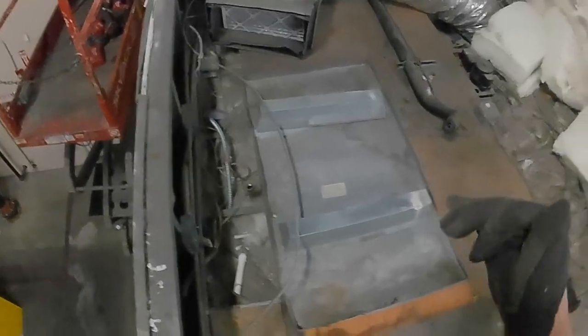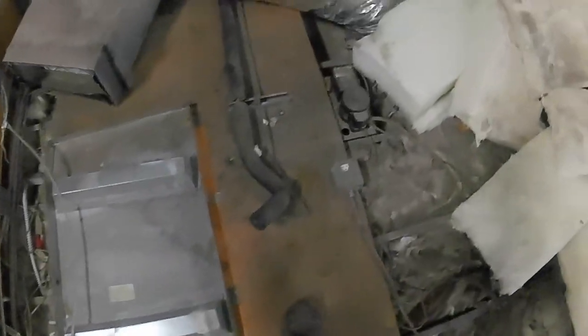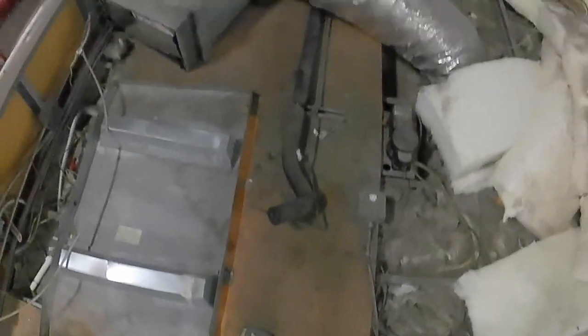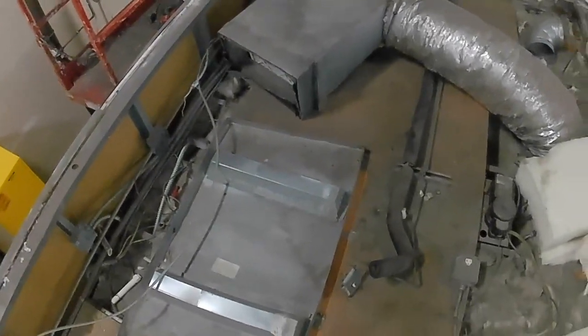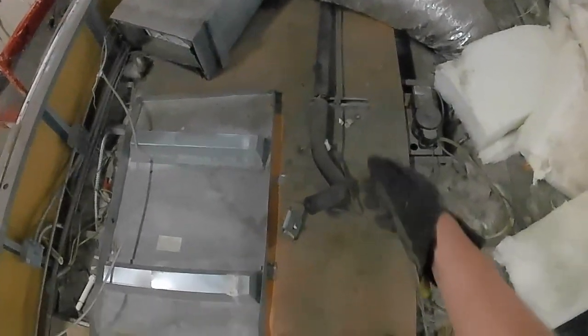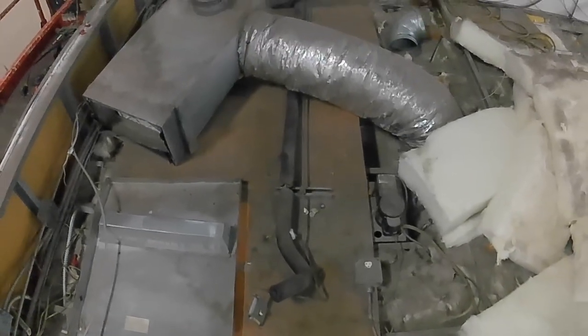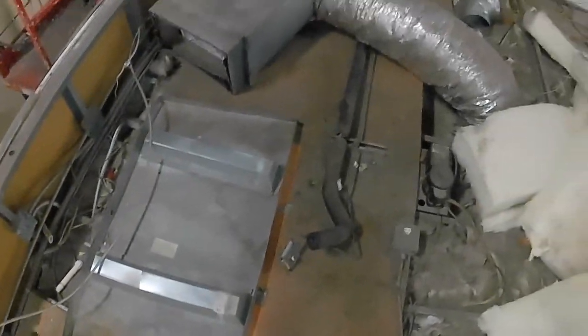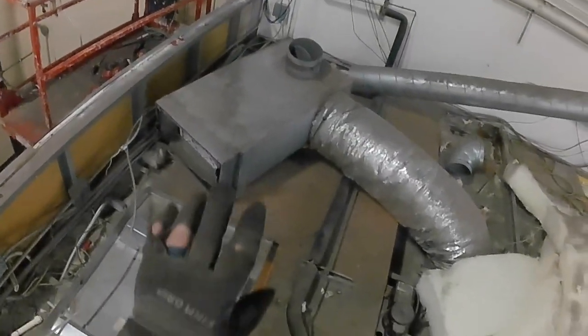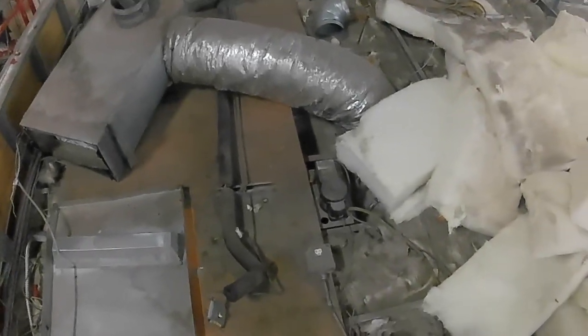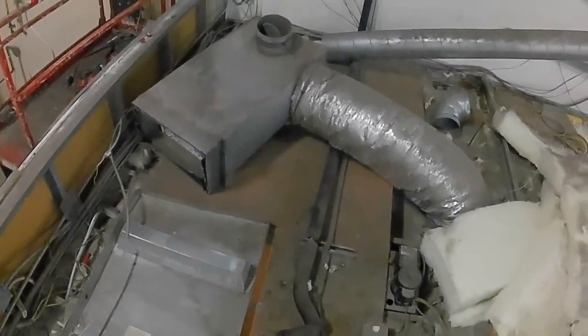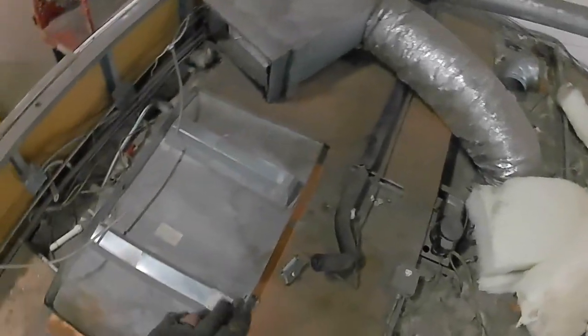All right, fellas, welcome back. So it looks like we got the air handler unit out of here. You guys watched the whole teardown, saw how everything went. I always made sure to verify if I have power or no power, that's probably the most important part, and the gas, the refrigerant. But I knew I had the pump down done already, so the only other thing would be to verify that this unit had no power. And of course, anytime you open a box before you start cutting wires, you're gonna take a reading.